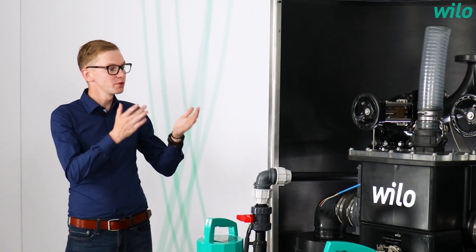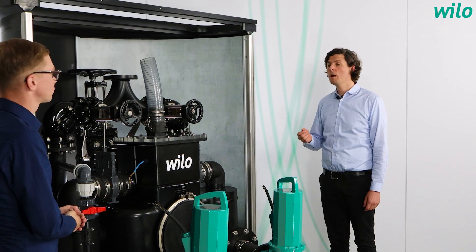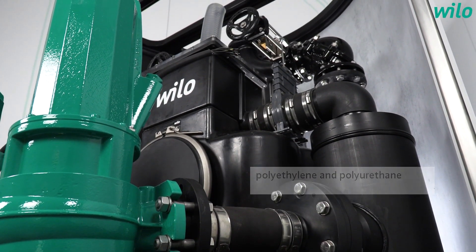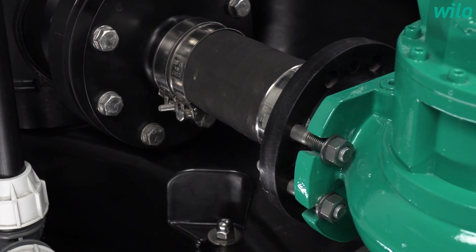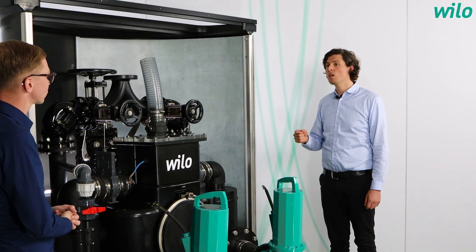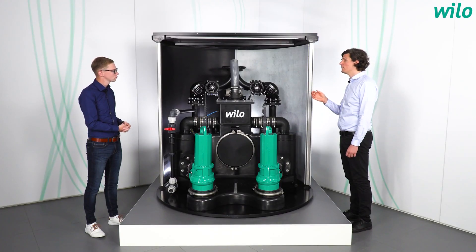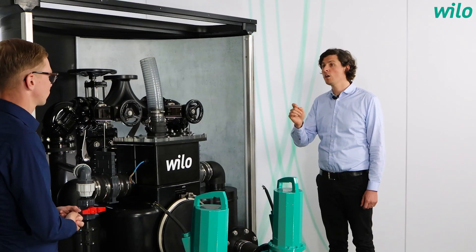And what is it about the material and the setup? Through the use of long-life corrosion-free polyethylene and polyurethane material, there is no danger of crevice corrosion or pinholing. Also, the pumps sit outside of the enclosure and therefore not in the medium, which means that wastewater hydraulics can be used with a higher level of pumping efficiency. For example, single channel impellers instead of vortex. This means for the customer a lower current consumption.